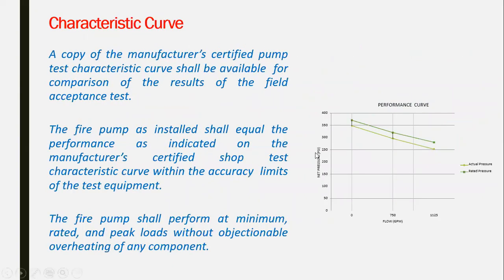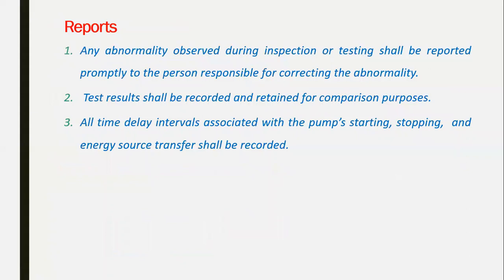This is the characteristic curve for the pump, showing the flow rate and the pressure, to compare with your readings. You take the readings during the test and inspection, and we have to compare them against the characteristic curve of the pump: what the pressure and flow should be, and whether the readings match the characteristic curve or not. Then prepare your report based on any abnormal observations during the inspection, or recommendations for any spare parts, etc.